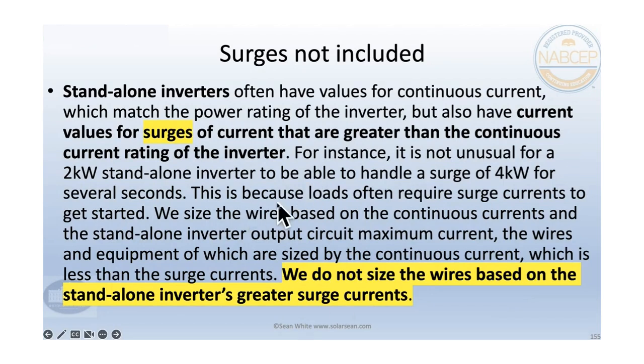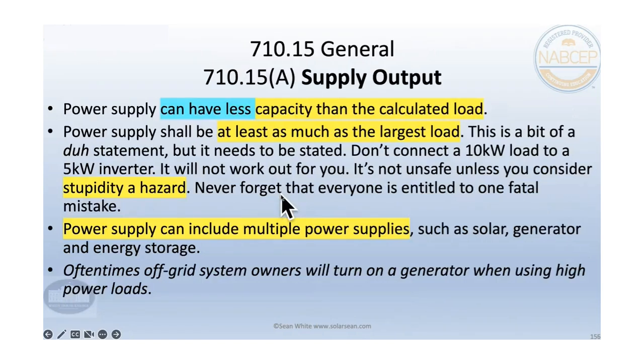You don't size wires based on surge currents. A lot of times the surge current can be double of what the continuous current. So you're always sizing your wires based on operating current, especially with standalone systems. That's where you're going to have these available surge currents.